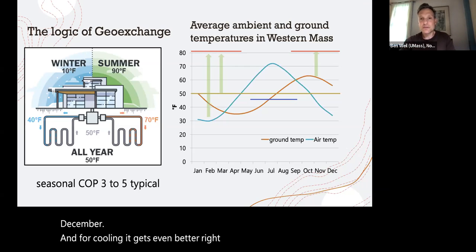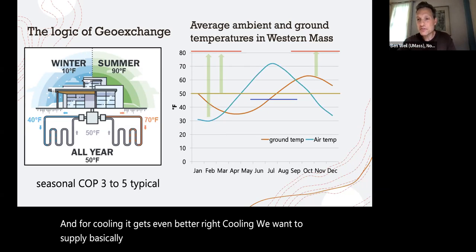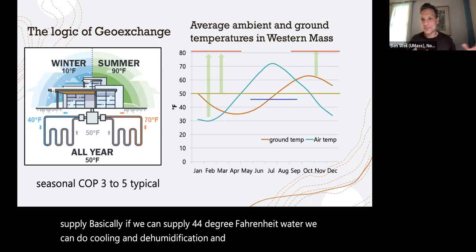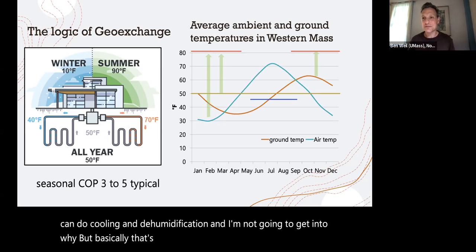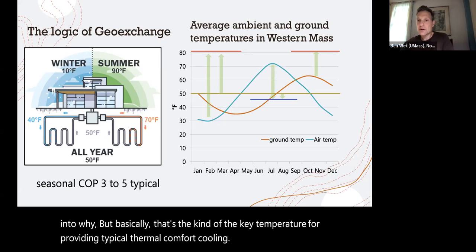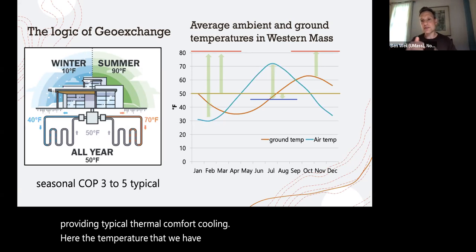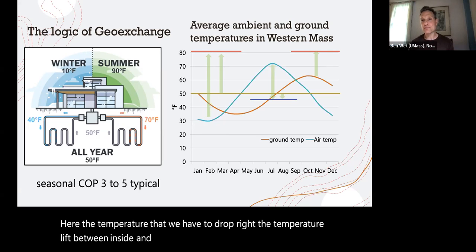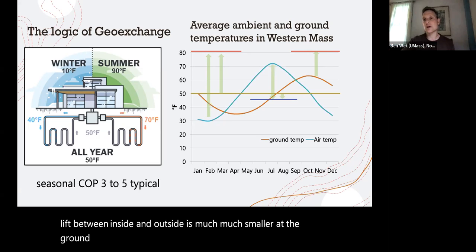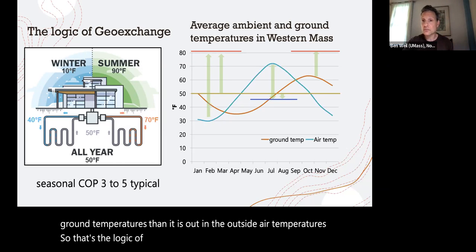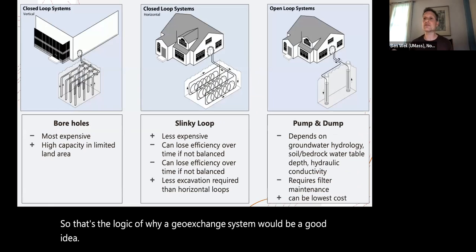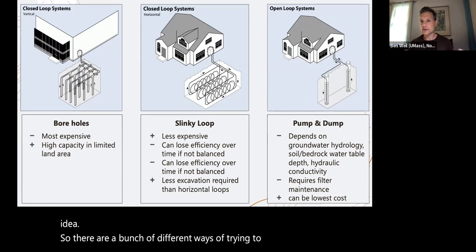For cooling, if we can supply 44-degree Fahrenheit water, we can do cooling and dehumidification. I'm not going to get into why, but that's the key temperature for providing typical thermal comfort cooling. Here, the temperature lift between inside and outside is much, much smaller at the ground temperatures than it is with the outside air temperatures. So that's the logic of why a geo-exchange system would be a good idea. There are a bunch of different ways of trying to exchange your heat with the ground.